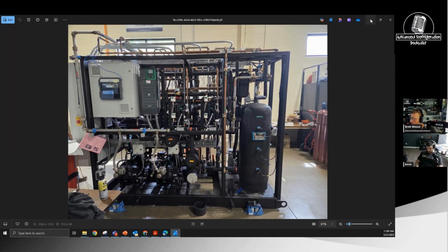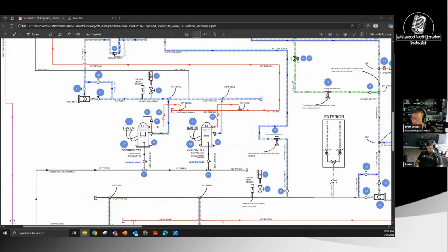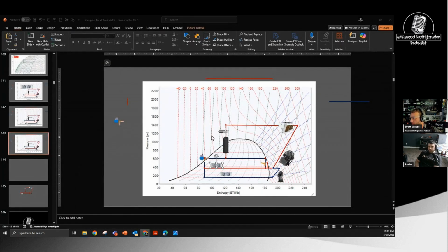Anything else you want to talk about with this bad boy? No, let's discuss this liquid on the drop leg. But the sight glass you were showing was the one before, though. Yeah, it was before, that's what kind of throws it off though. We can, but it was before the valve. And then after the valve too, I was showing it, there was a lot of liquid after the valve still.